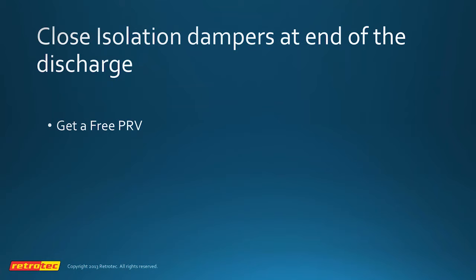Another option is for existing enclosures. Often there are isolation dampers in the room that are designed to isolate the enclosure from the rest of the building or the rest of the HVAC system. And in some cases, by changing the damper closing sequence, you can get some free venting, essentially by, instead of closing the dampers before the agent discharge, closing them after the end of the discharge. And it's somewhat counterintuitive. People like to close the enclosure off and then discharge.